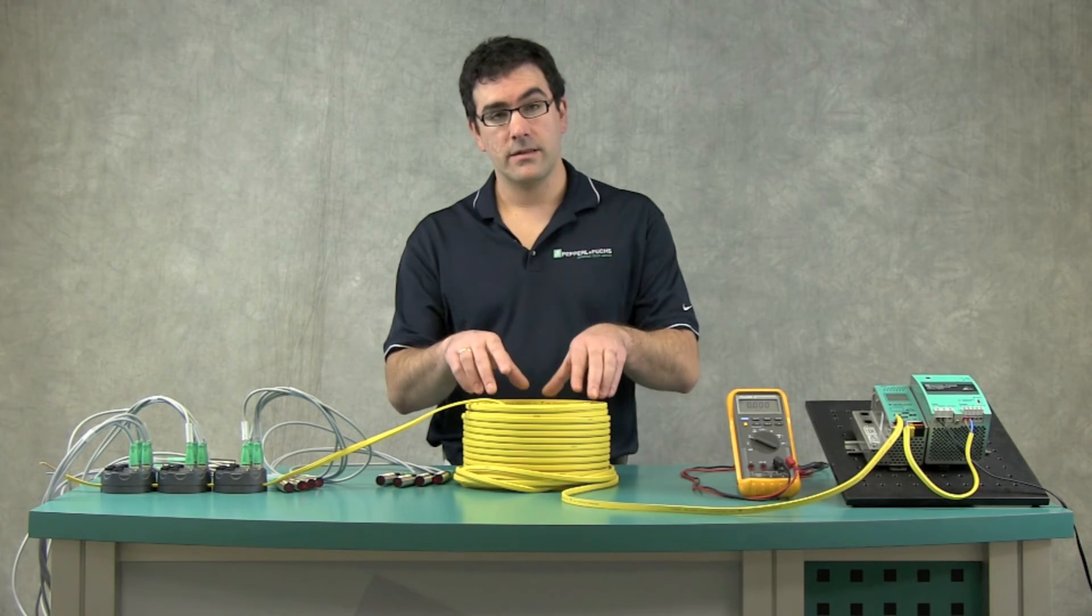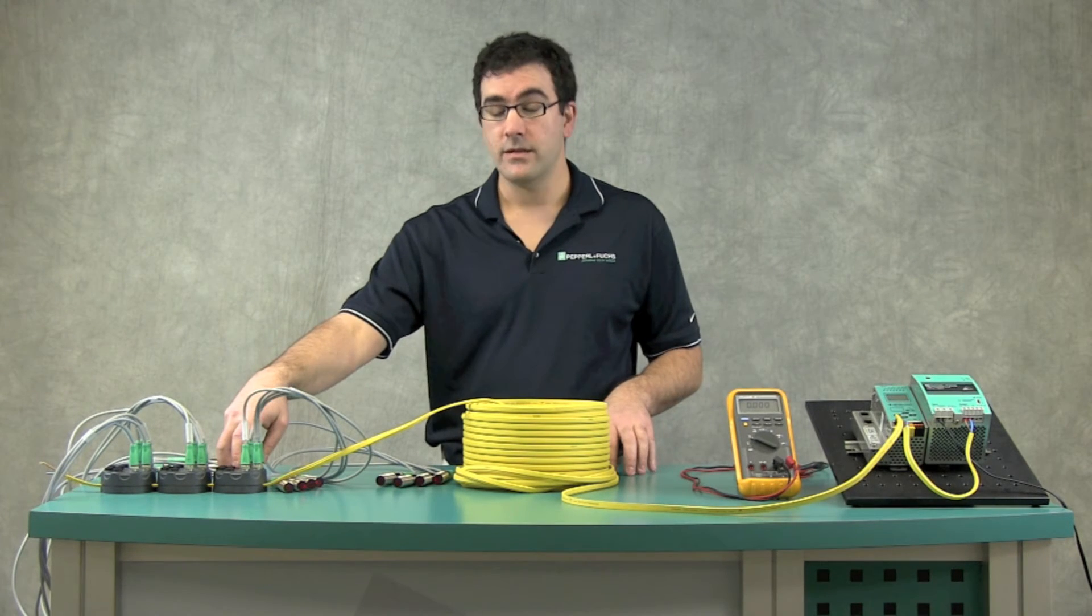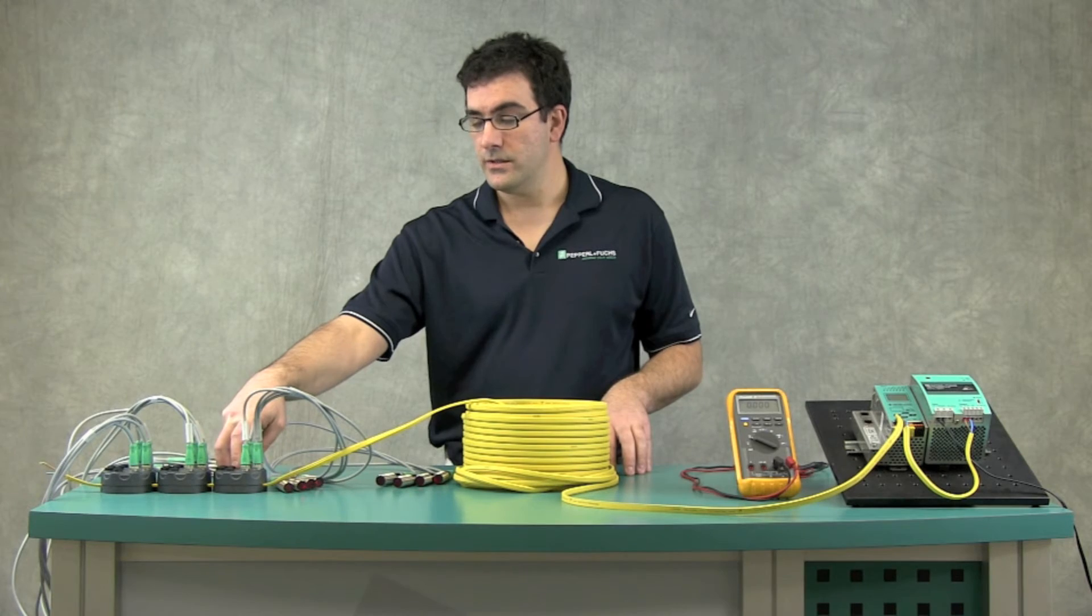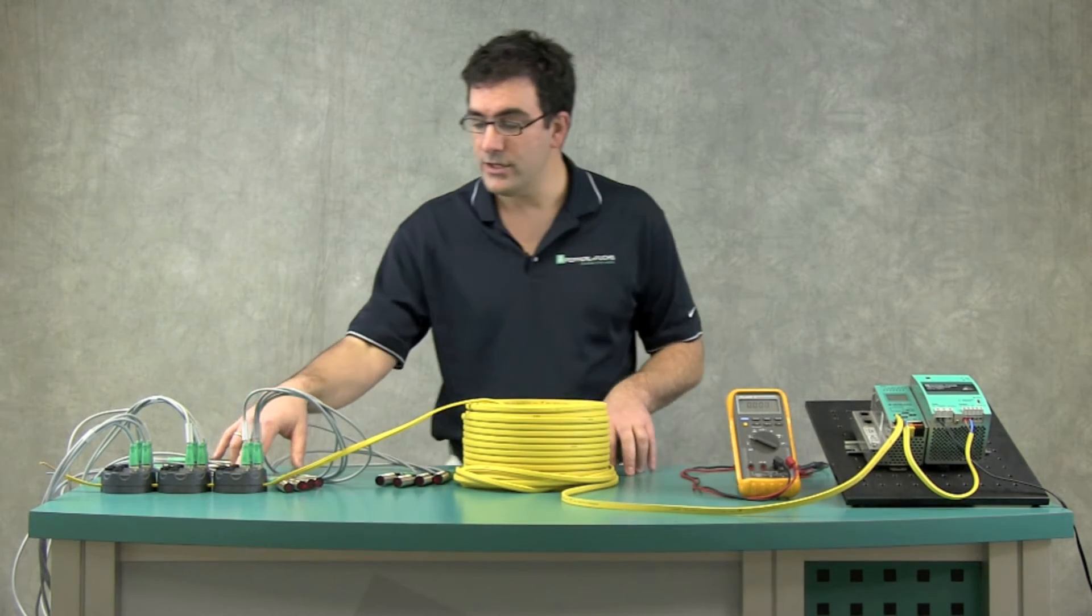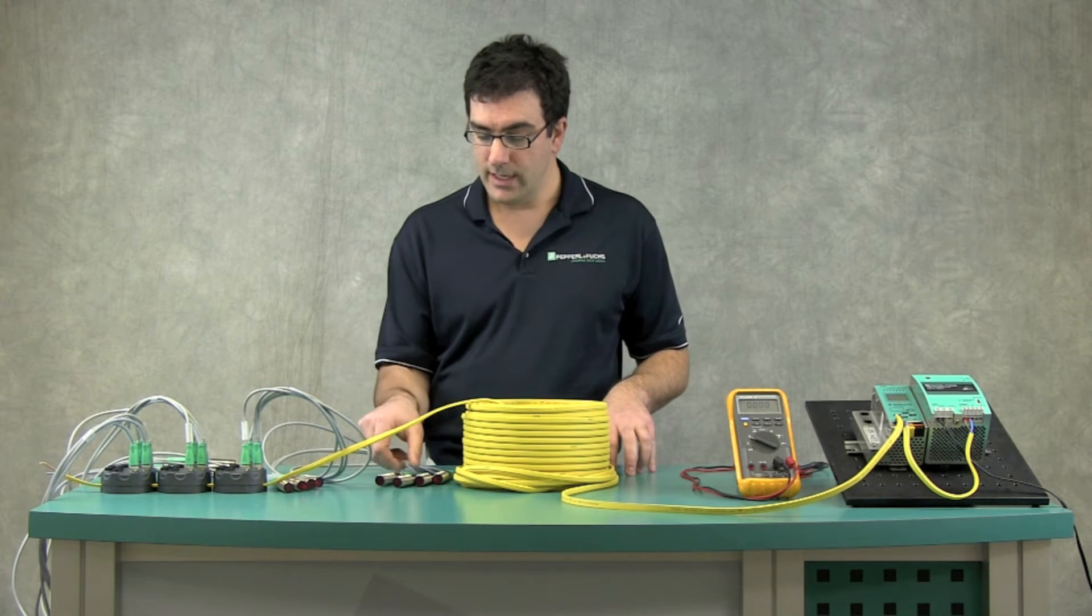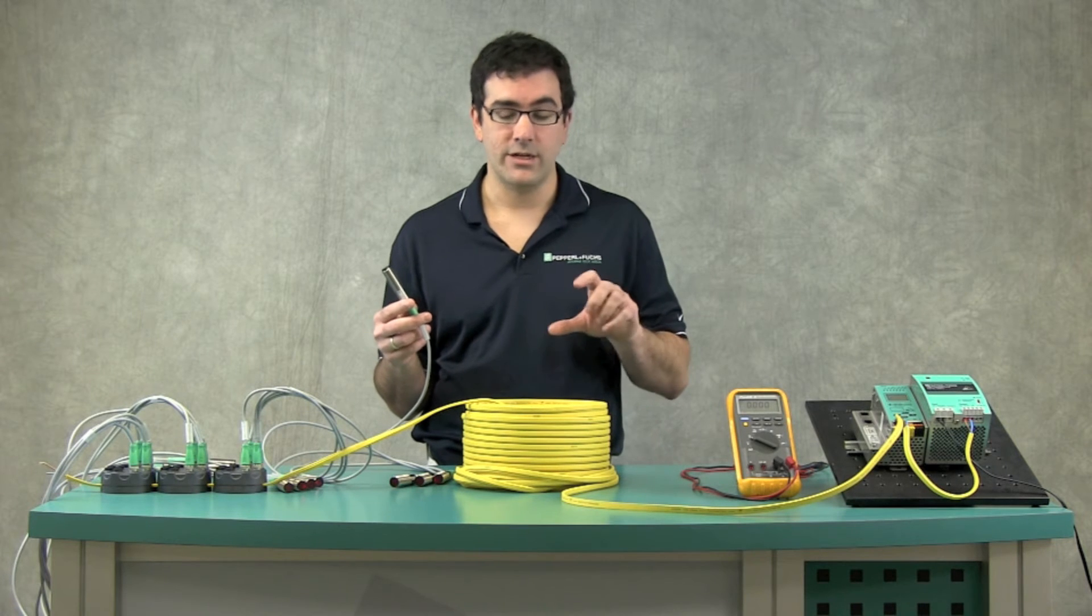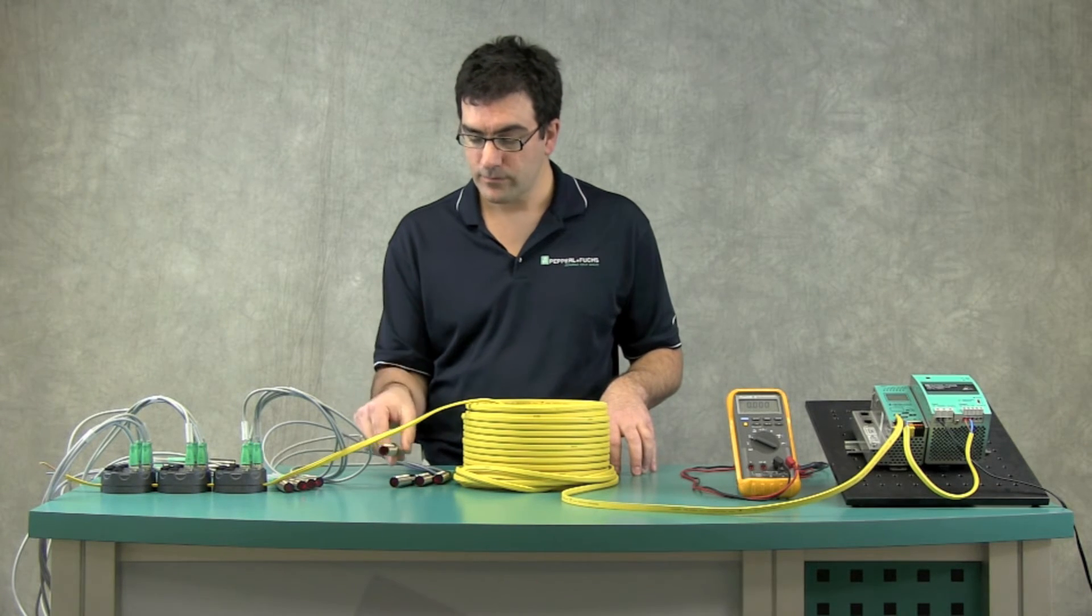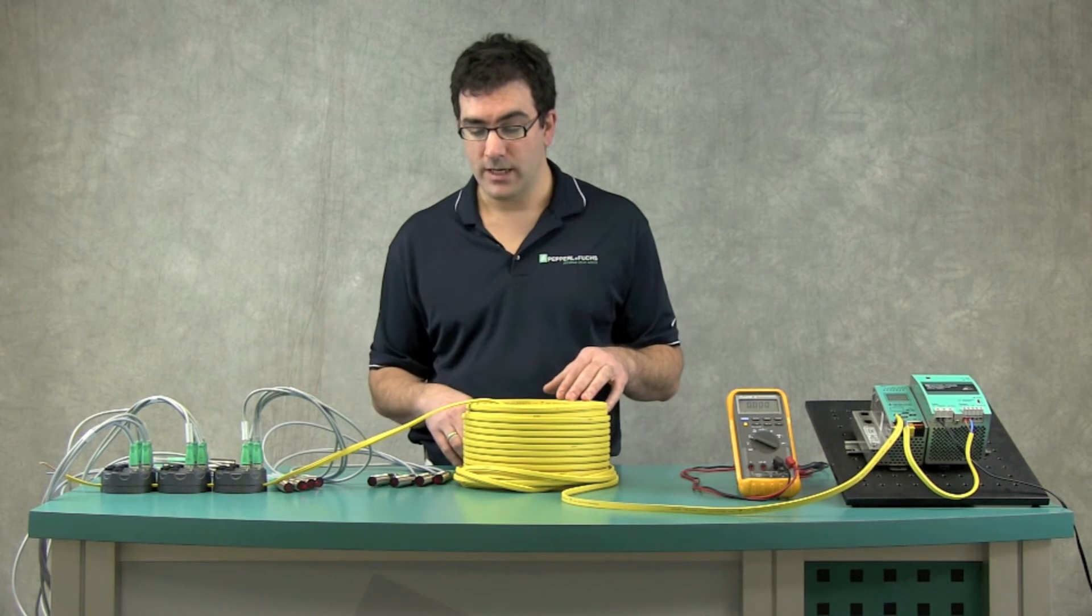All you're going to need is the length of the cable, in this case 90 meters. You're going to need the model number of the ASI module, which is VBA-4E-G11-ZA-JF, in this case. You've got three of those. And you're going to need the operating current, the no-load operating current, as on the datasheet of these VT18 sensors. Once you have that, you can load everything in, and it will automatically calculate what the voltage drop will be.